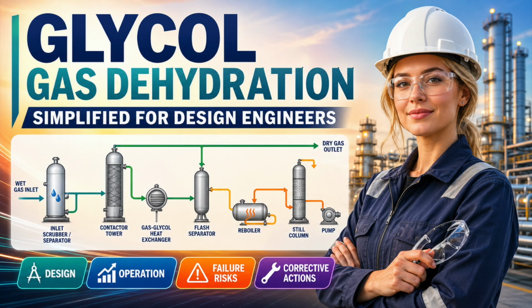The reboiler is where glycol is regenerated, but it is also where glycol can be destroyed. Water is boiled out of the rich glycol, but excessive temperature or local overheating causes degradation. Bulk glycol temperature must therefore be controlled, and the fire tube must be designed with sufficient area to avoid excessive heat flux. You should never review a reboiler only by checking total heat duty. The proper review includes fire tube surface area, heat flux, heat density, burner geometry, flame pattern, wall temperature, fouling tendency, fuel quality, stack draft, site elevation, and access for inspection.